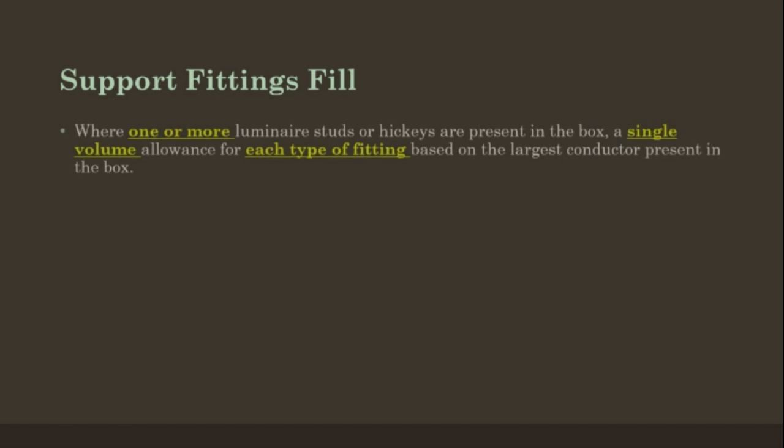Supporting fittings fill. These are support fittings, fixture hickeys, etc. Where one or more luminaire studs or hickeys are present in the box, a single volume allowance for each type of fitting, based on the largest conductor present in the box.